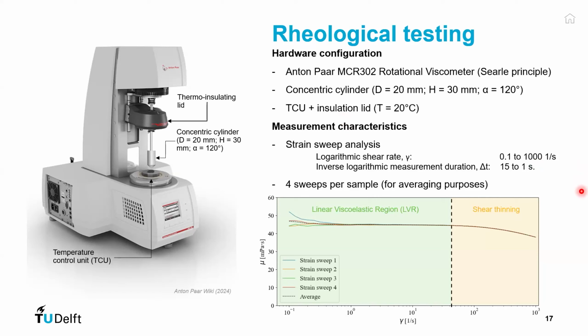So starting with the first part in terms of the hardware, we're using a rotational viscometer by a manufacturer called Anton Paar. The specific type I've also highlighted here, but they come in many different versions. And this one uses the Searle principle in order to measure the viscosity. Later on in this slide, I will come back to this, so I will park that for a second. The device is shown over here. So we have a concentric cylinder, which will essentially go down into a small measurement cup that contains our fluid. The dimensions of this cylinder are listed over here. Subsequently, it will start to spin, exerting a certain force on the fluid. And then from a small equation, I will come back to this as well, we can then calculate the viscosity.